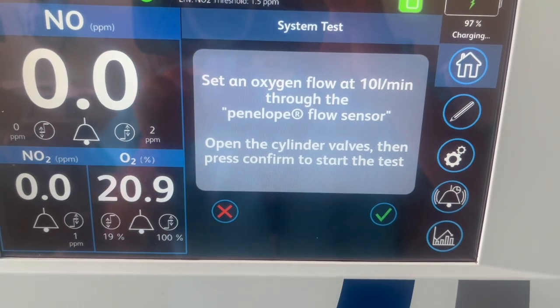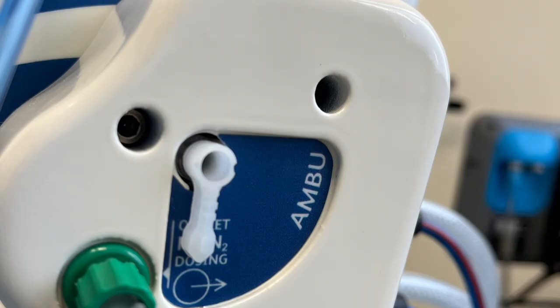To give you the best chance of passing the system delivery test, you must first do a few checks. Go to the side of the machine and ensure that the switch is facing down away from the ambu bagging setting, otherwise the system delivery test will fail.